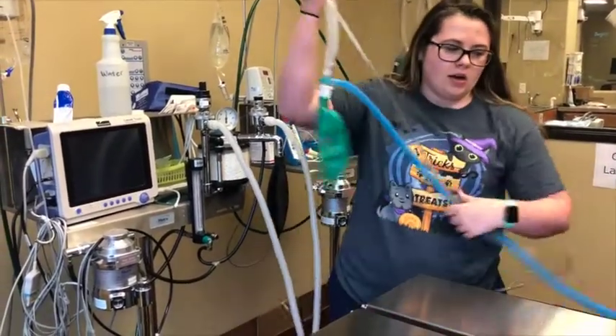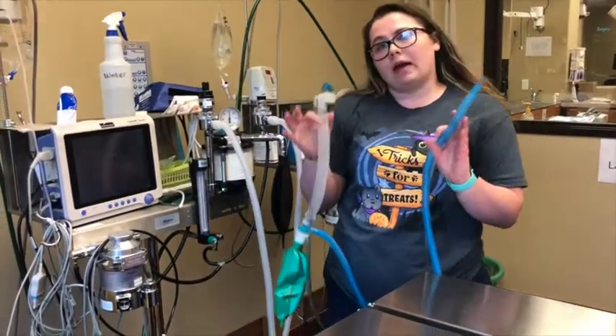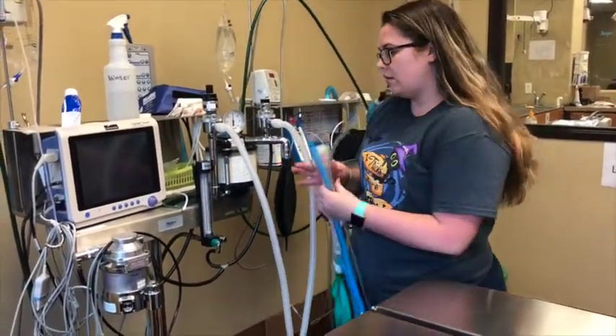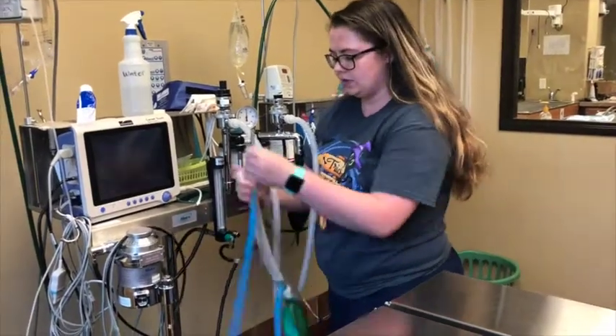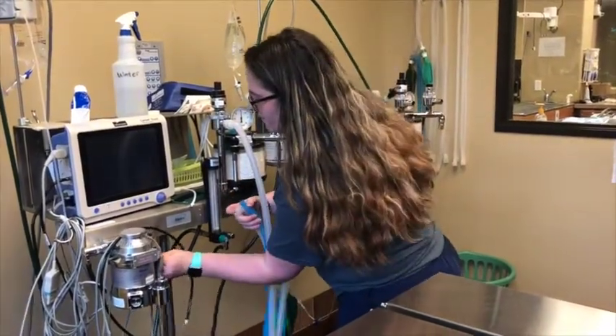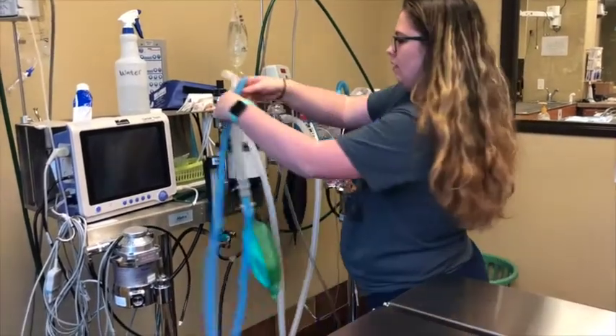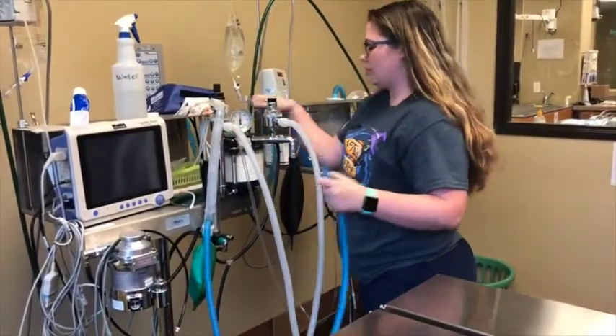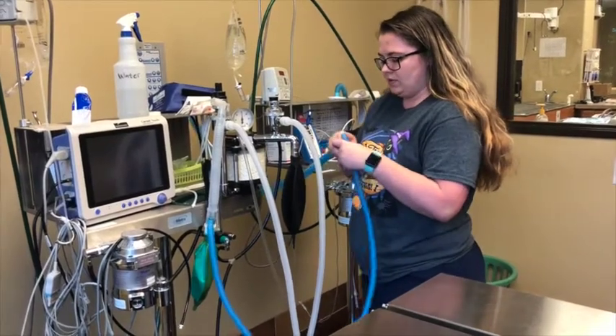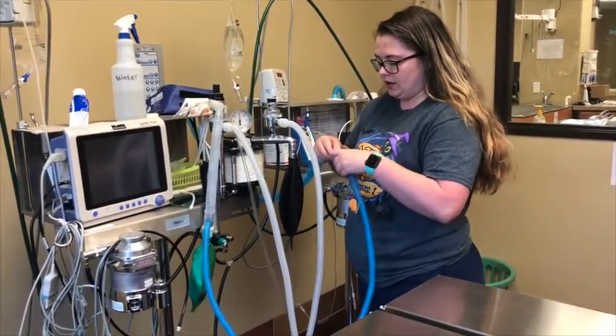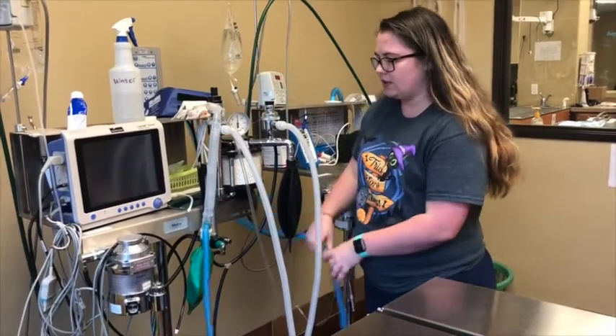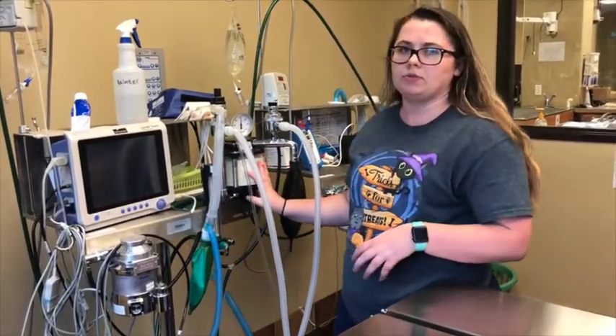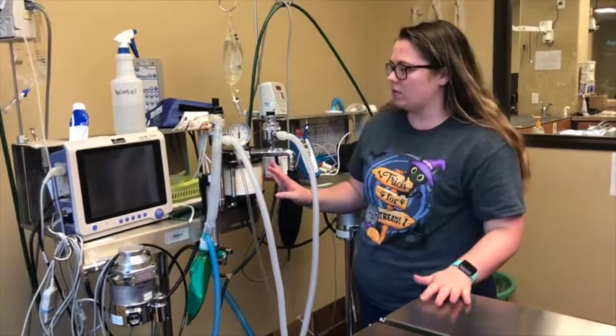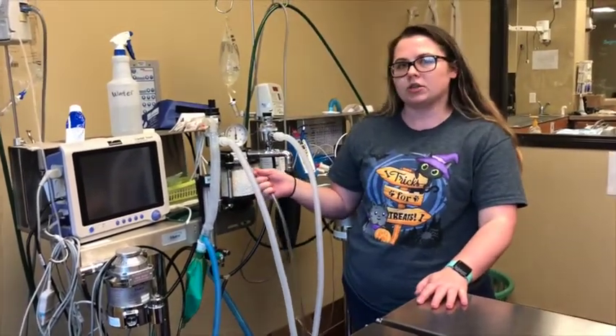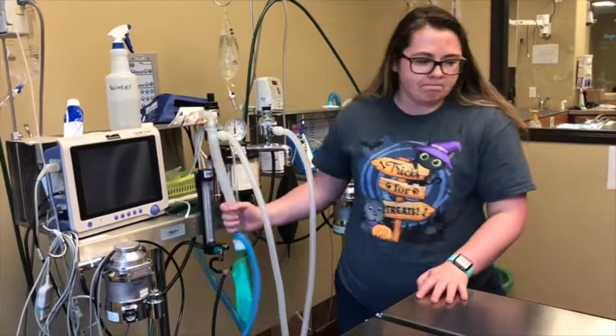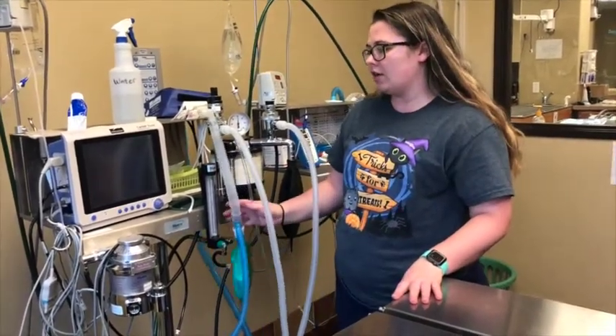Our next thing here is our non-rebreathing, or the Bain. When this is hooked up, we'll take this clear tube, hook it up here, and then our blue tube will go to our SodaZorb canister and hook up this way. This is our non-rebreathing system, so it is bypassing our CO2 absorber. It will not absorb the carbon dioxide. You only use these for patients under 12 pounds, so we don't use these very often.